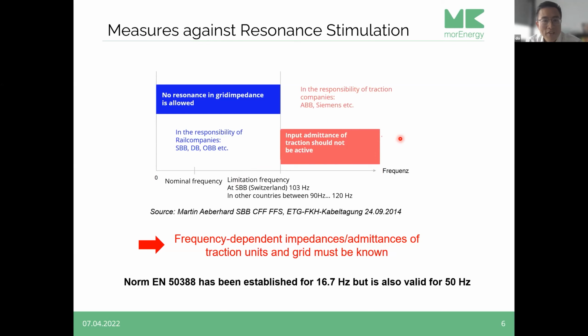On the right side, there is a definition that the input admittance of the traction should not be active. That means the admittance, or also the impedance, of the electrical system has to be measured. And the phase of the admittance should not exceed plus or minus 90 degrees. This is what the right side says about that.